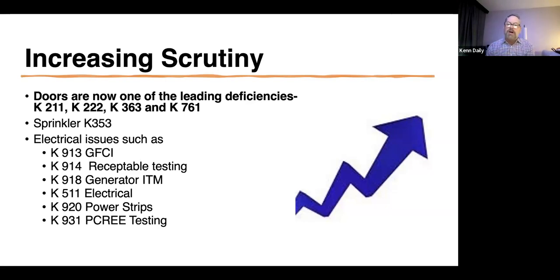And then the third issue of ever increasing importance, and it could actually be number one very soon, is going to be electrical issues. Generators are off the hook important, whether it's the wiring for your generator and making sure you have the 3 branches, the life safety, critical, and equipment branch, or the testing of your generator: weekly visual, monthly exercises, 3-year exercise, etc. Or the other electrical issues, such as non-hospital grade receptacle testing, or GFIs that are working or in the right locations, the use of power strips and extension cords.